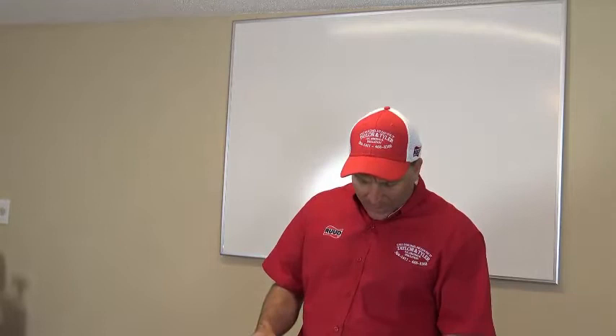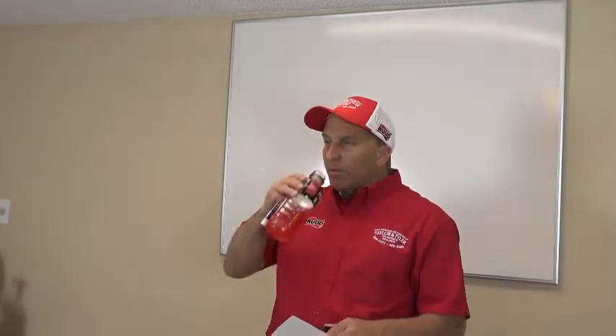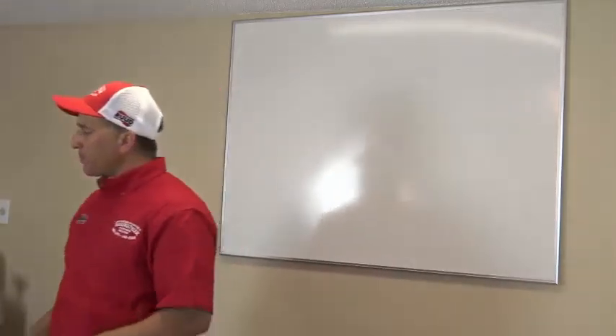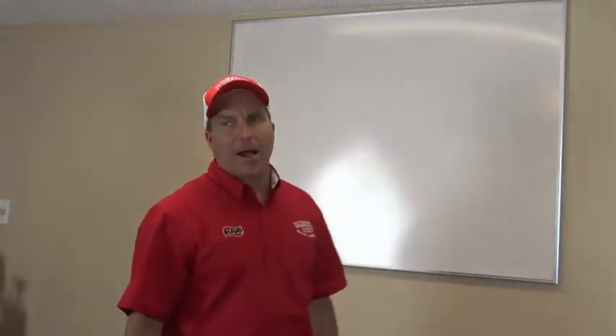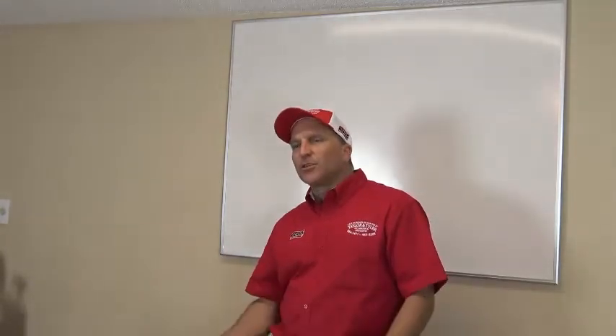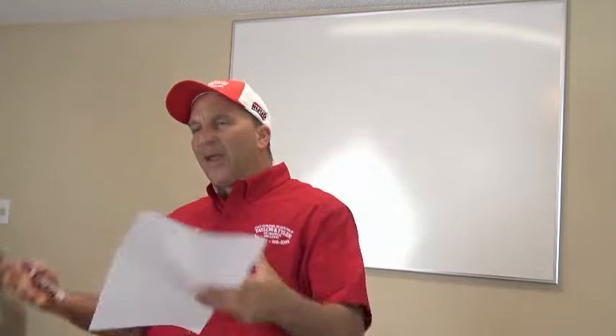Your compressor, is it okay? Is it sweating or is it rusted? If your compressor is rusted, that tells you the history of that compressor. How does your compressor get rusted? Your compressor gets rusted because it's been sweating a lot. That tells me you had a dirty evaporator coil, probably. System's been running and the liquid has been getting into your compressor, causing your compressor to sweat. When it continues to sweat, the sweat ends up causing rust, and then it starts to take all the paint off of it.